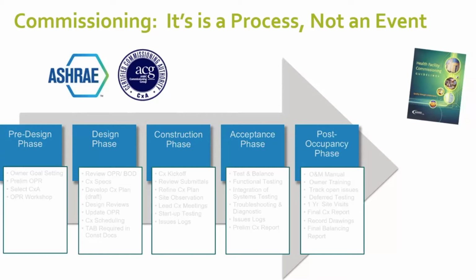In addition, we ensure different equipment work together as part of the building system. For instance, with solar panels, we construct startup checklists and performance tests to make sure that in the event of a power outage, it seamlessly integrates with the backup energy system in place. If there's a generator, we also make sure the building's energy needs are met first by the solar panel and battery storage before having to turn on the generator.